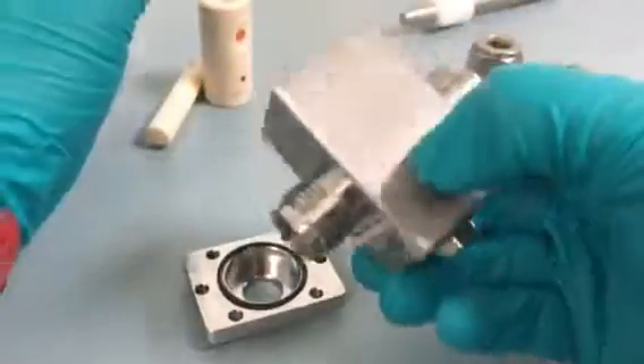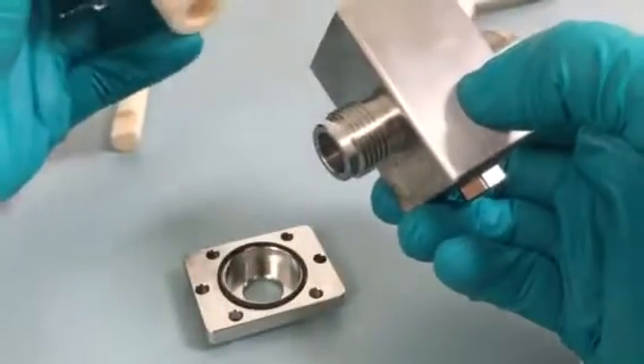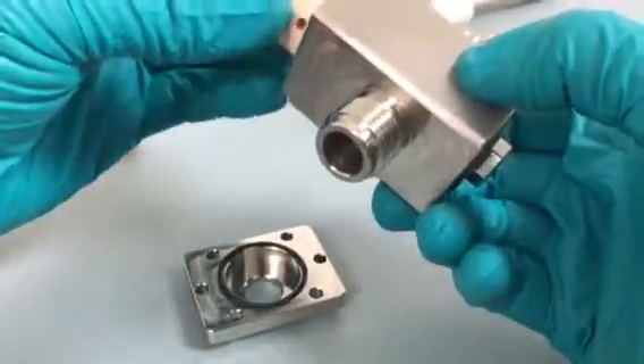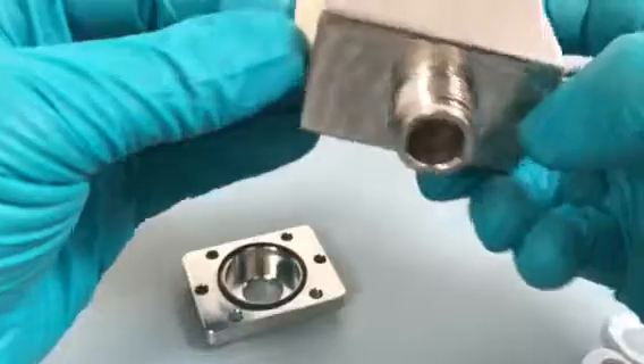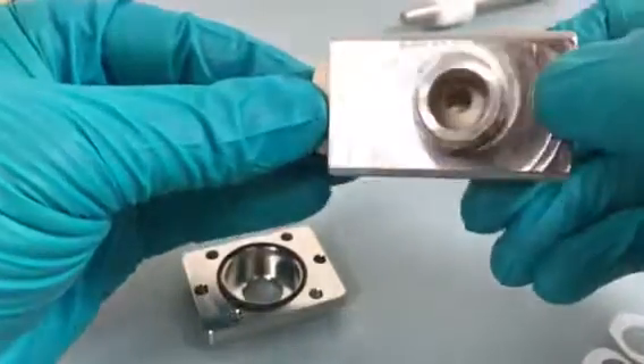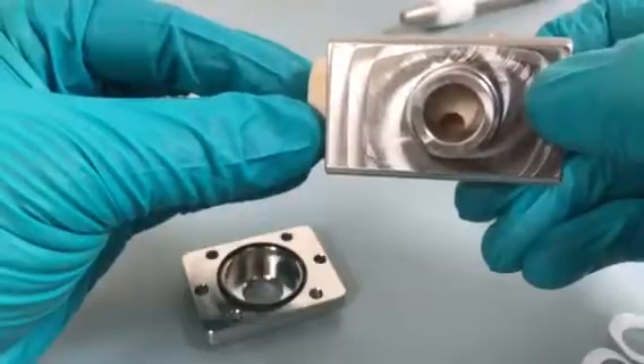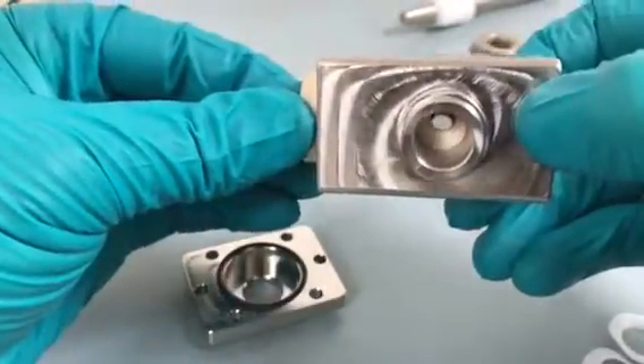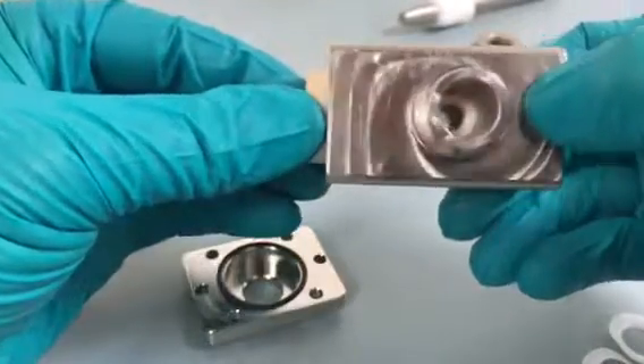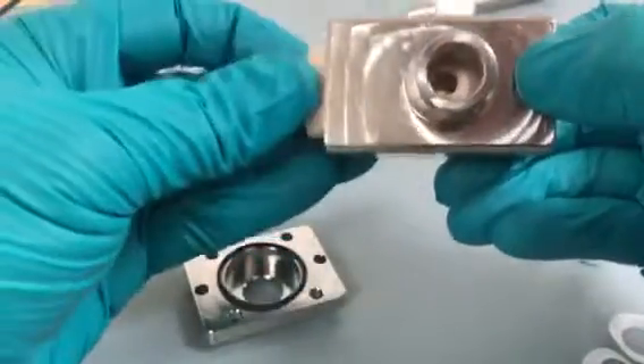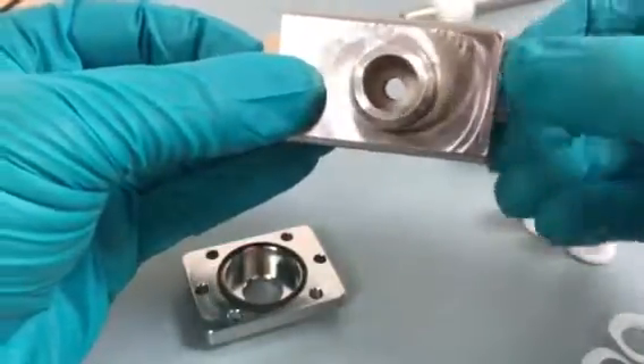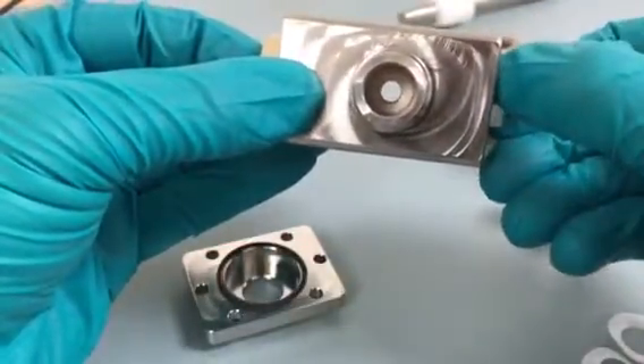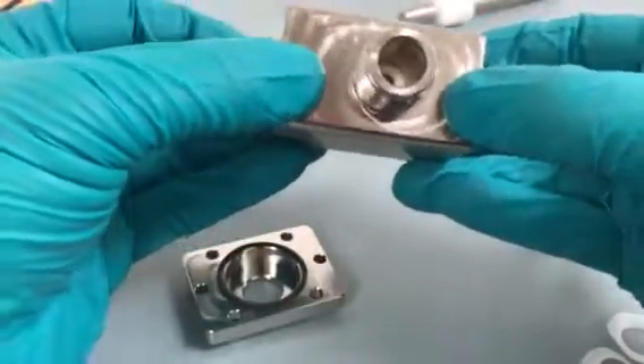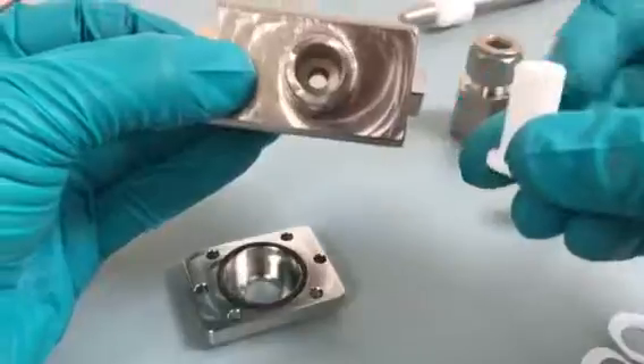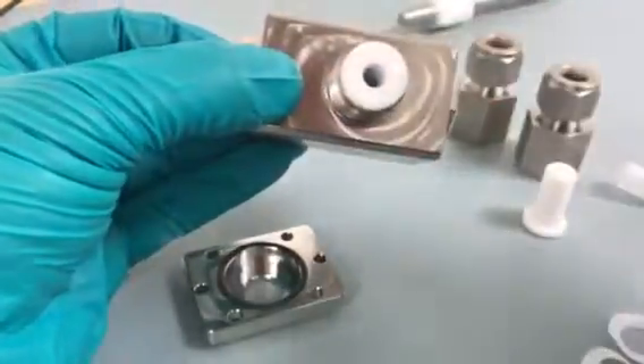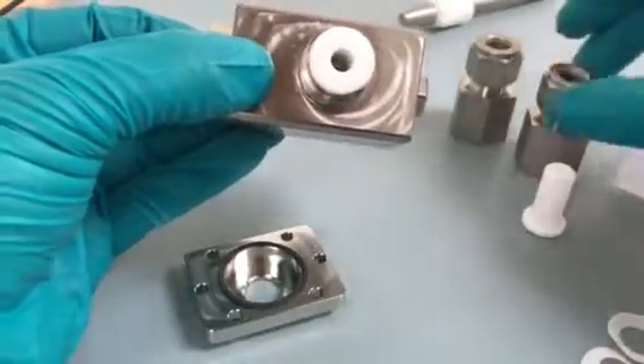Next, we will insert the ceramic liner with the ports down towards the ports of the pump body, and we're going to assure that we don't have this or this clocking. We're able to see through. We can use our cap screw also to adjust that position. So we're going to center that. We're going to then use one of the port seal bushings to locate that ceramic liner.